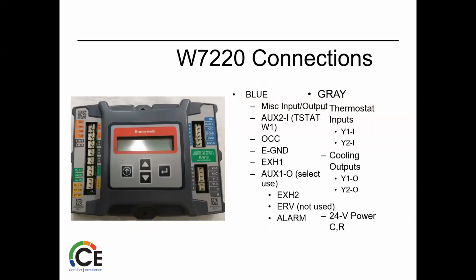Basic wiring, won't go through this too much. Your blue and gray side, again, just like in the other control, is on our 24-volt side. This is our inputs and outputs going through here. Occupied if you need it. Ground, definitely need the ground. EXH1, auxiliary 1. Here's your alarm control. Obviously, you can see the gray ones have your thermostat on it. Your inputs and outputs for that same operation.